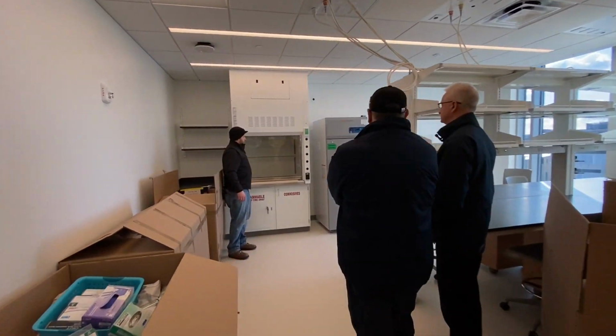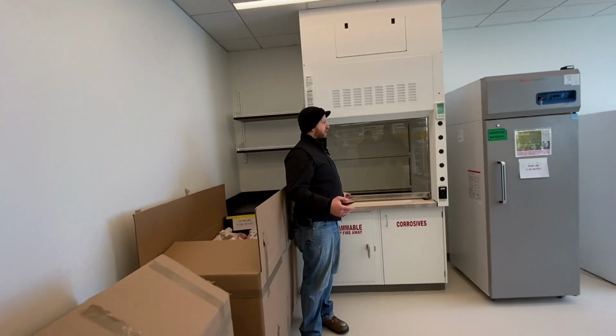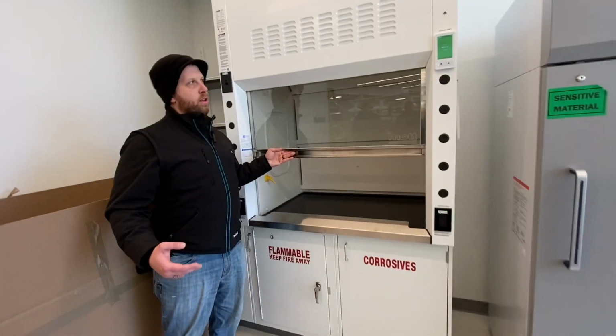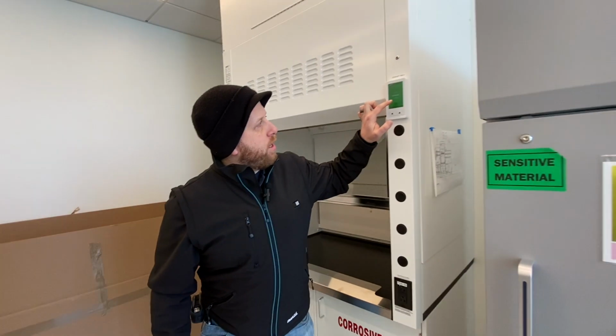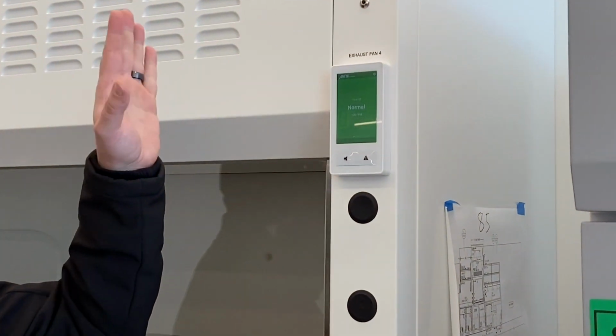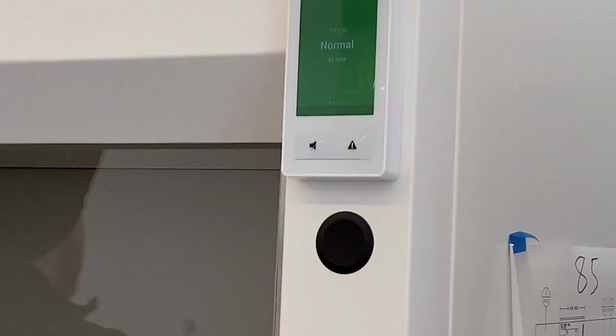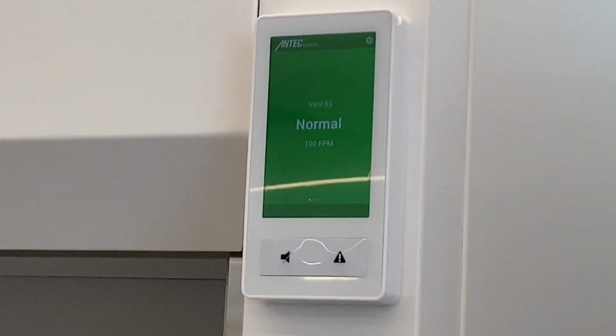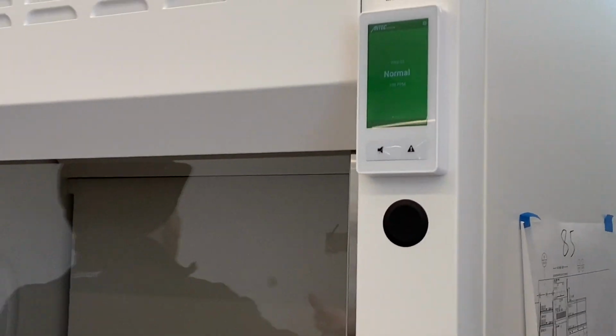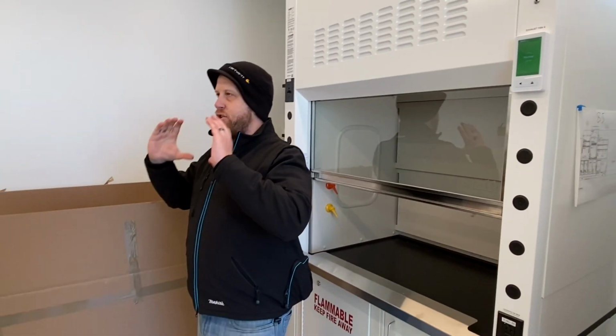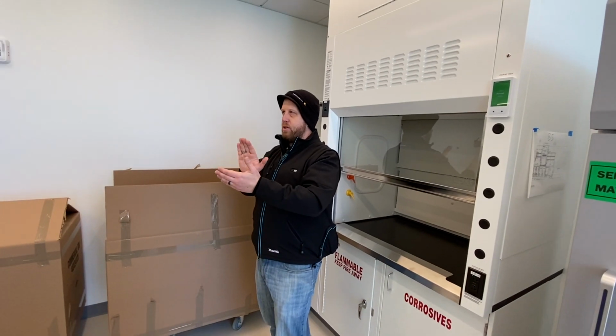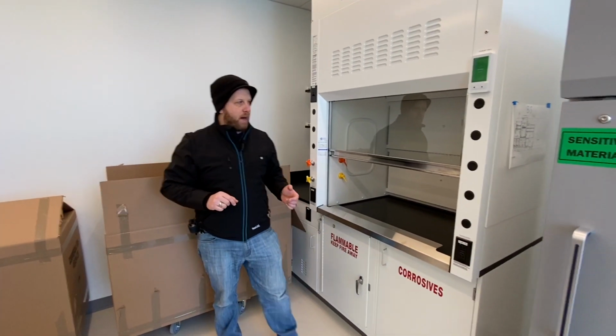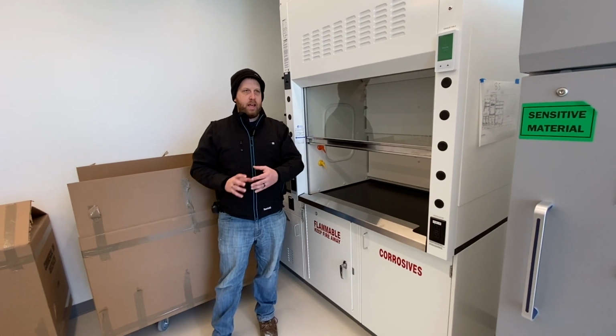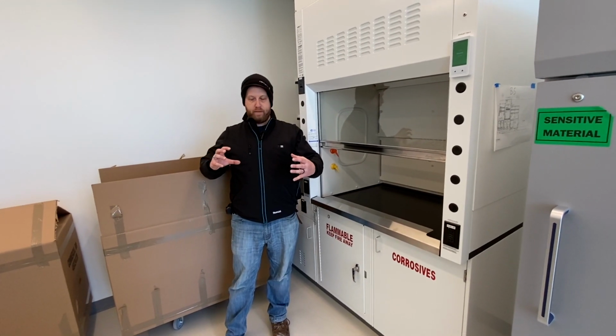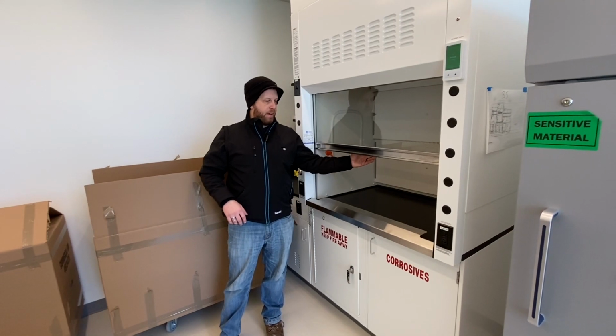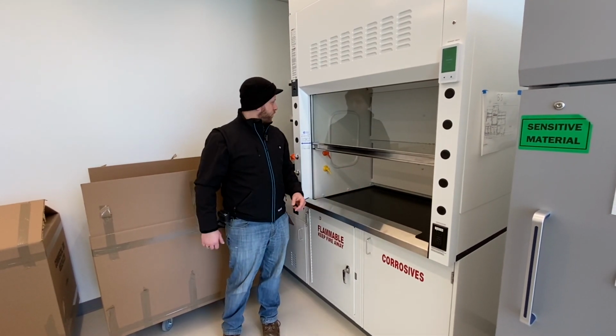So I'll show you. Just so you know, as they open these hoods, and you can hear it, the Antec will increase. Now the fume hood exhaust air valve, and when I say it's an air valve, it's different from a typical VAV box with the rotating damper. It's a plunger style. It goes in and out. So it's a Venturi valve, and as the plunger goes in, it restricts the airflow. So it's a little bit different than a typical VAV box. But as you open this, the air valve pulls out of the throat of the Venturi valve, and more air is brought across the face velocity sensor.